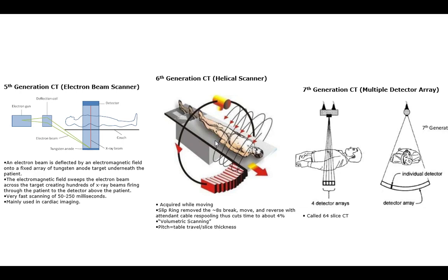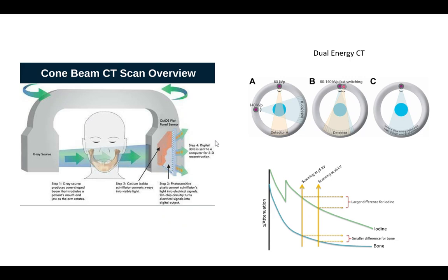Okay. Alternate types of scanners that are out there. We've mentioned cone beam CT before. So imagine I don't want to have to move. Right? So now I take an appropriate cone. I don't have to take one slice, I'm taking the whole thing. So now I put an array of detectors over here, and I have a cone source going through. This is done in a lot of dental work, but it can be used in other areas for any reasonable section of the body. And I just take one rotation, and I get a whole bunch of slices through the cone. Right? So effectively, I don't have to do the transverse part.